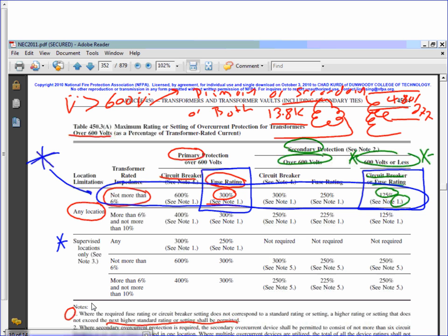Let me just explain. That's another table similar to the one that we were just talking about. When you guys go there, you only use this table, which is the A, if the primary or the secondary is more than 600 volt. Is the primary or the secondary more than 600 volt? Yes. The primary, yes. Then you can't go to the B, to the table that says B. You have to go here. How do you use it? This one says any location. This is supervised locations. What's a supervised location? Supervised location is when the building has its own crew of qualified maintenance electricians sitting there maintaining, troubleshooting and monitoring the system at all times. Industrial plants and what's not. All other applications, so this is supervised. You don't go to supervised unless you know it's supervised. So any location, your default is any location.